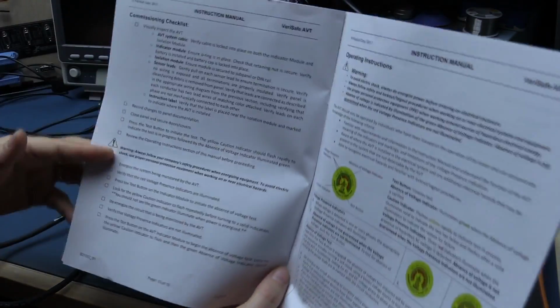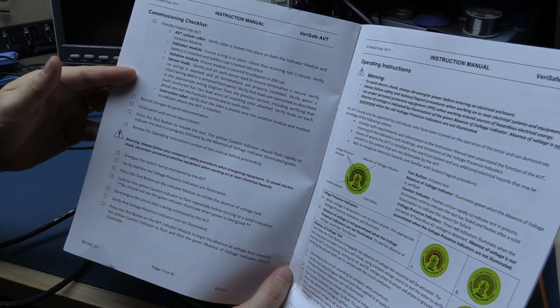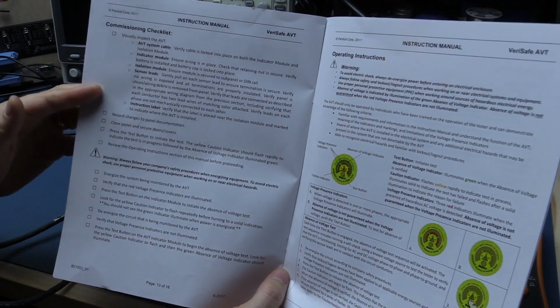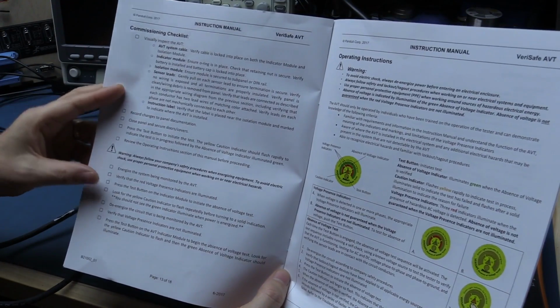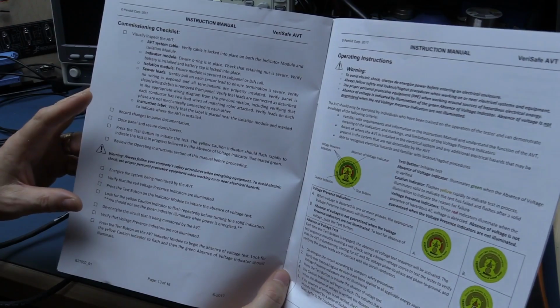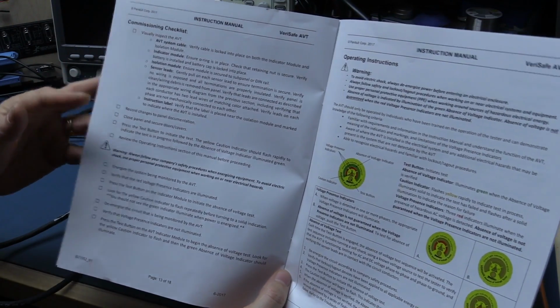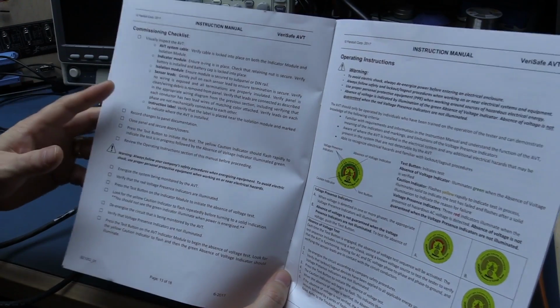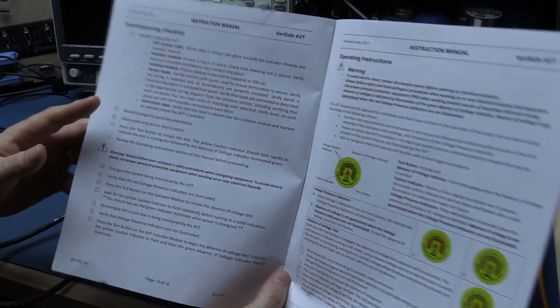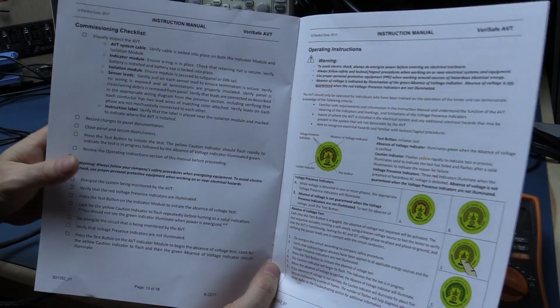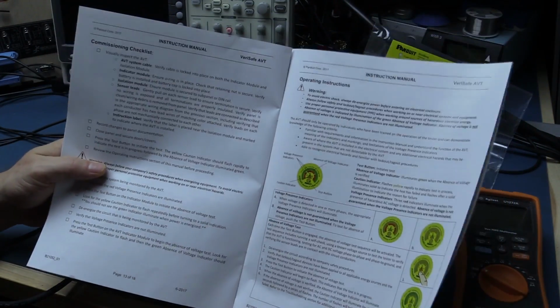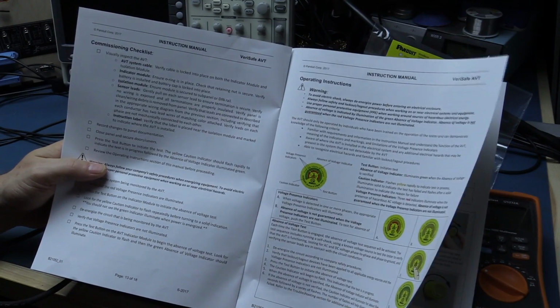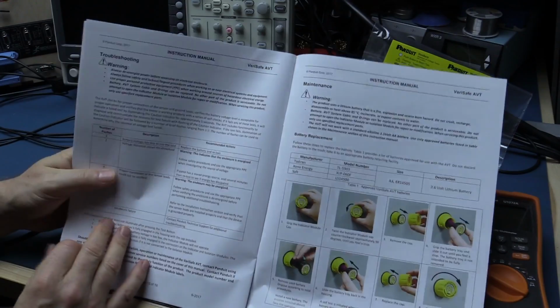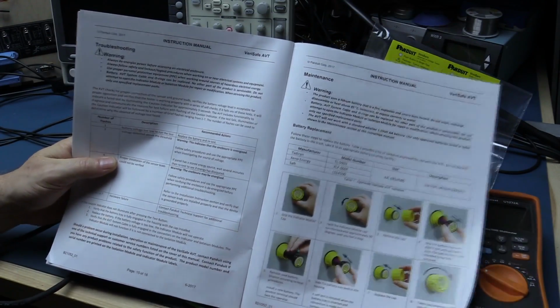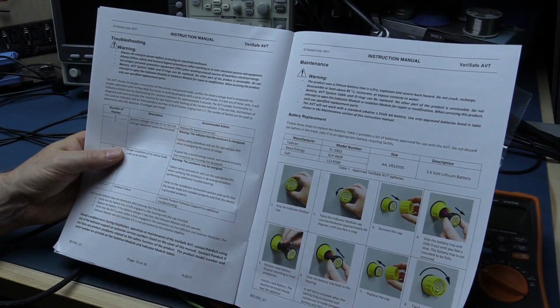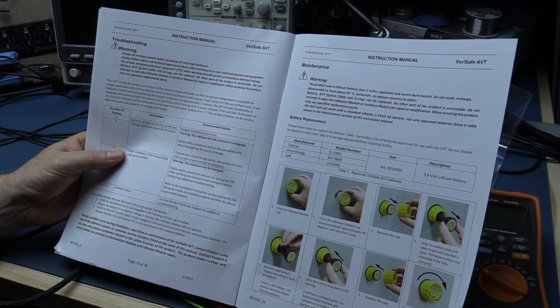Then an extensive commissioning checklist, which includes testing the system to be powered off the old-fashioned way before you go wire the new tester into the system. Remember what I said - test your multimeter, go to the circuit under test, then retest your multimeter to make sure it's still working before you decide that circuit has truly been turned off. Many times you might test your multimeter, travel to the place of work, only to find your multimeter got banged, bashed, your wire broke or something, and you think it's safe when it's not.